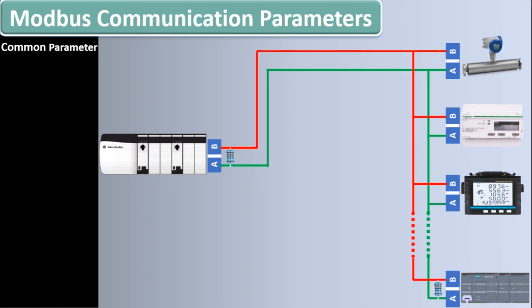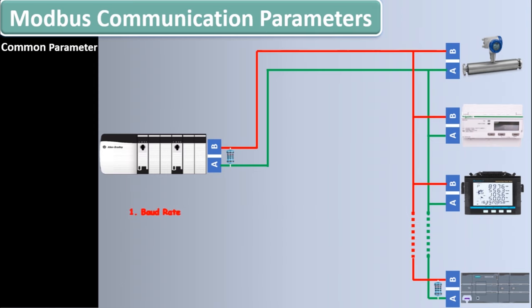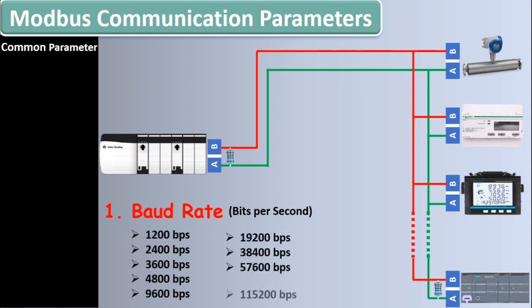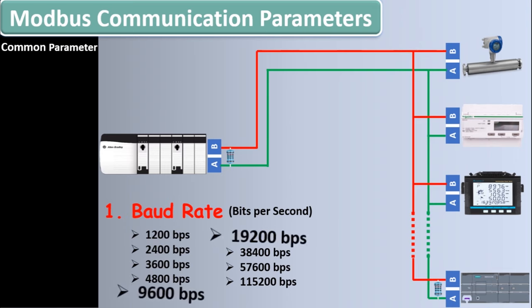Once the wiring is done, the first and most important parameter you must know about Modbus RS485 communication is the baud rate. All devices in the same Modbus loop must have the same baud rate. Baud rate is the rate at which data is transferred on the RS485 network, with a unit of bits per second. Different baud rates range from 1200 bits per second to 115200 bits per second, including 2400, 3600, 4800, 9600, 19200, 38400, and 57600 bits per second. The most commonly used baud rates in Modbus communication are 9600 and 19200 bits per second.